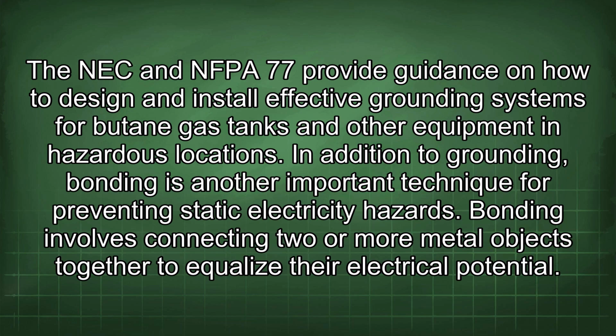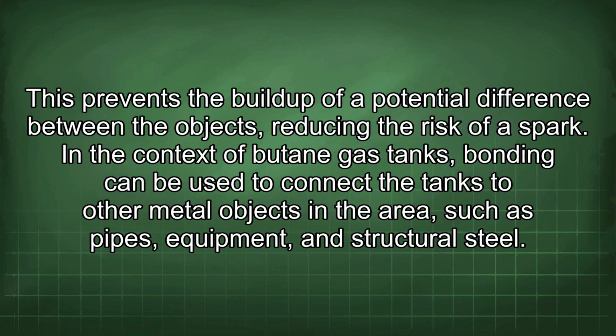In addition to grounding, bonding is another important technique for preventing static electricity hazards. Bonding involves connecting two or more metal objects together to equalize their electrical potential. This prevents the buildup of a potential difference between the objects, reducing the risk of a spark. In the context of butane gas tanks, bonding can be used to connect the tanks to other metal objects in the area, such as pipes, equipment, and structural steel.